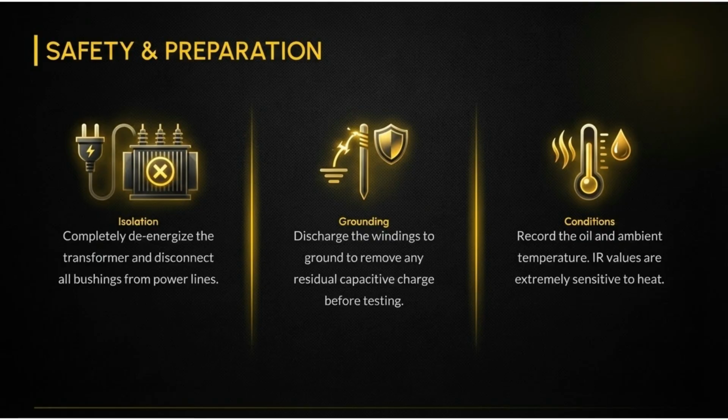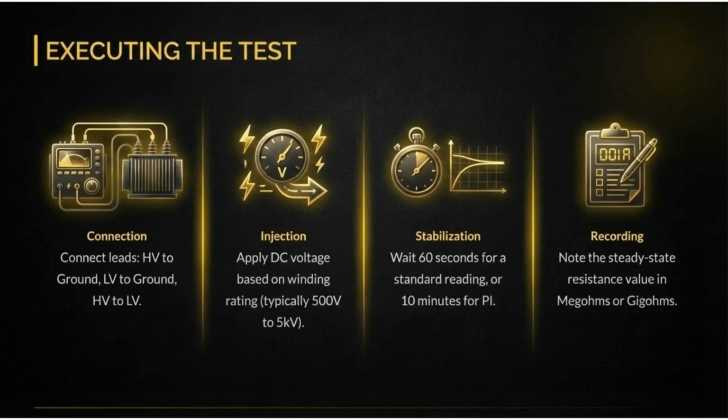Third, record oil and ambient temperatures, as IR values are sensitive to heat. Executing the test involves 4 steps. Connect the leads: HV to ground, LV to ground, and HV to LV. Inject DC voltage based on winding rating.